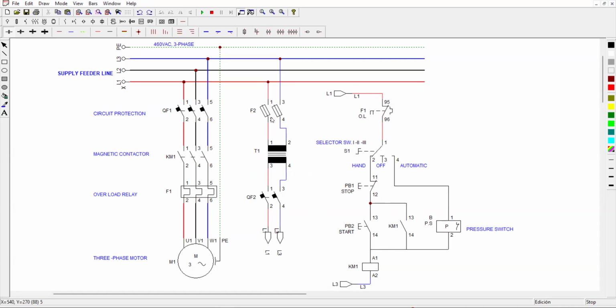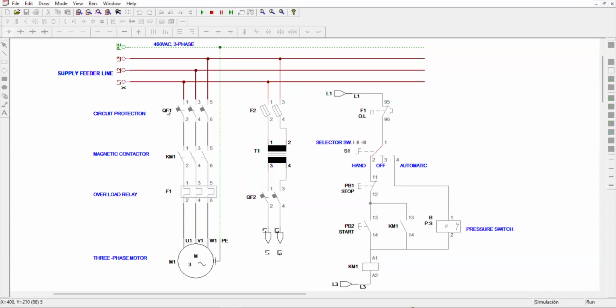So all in all, this will be our circuit diagram for the automatic and manual operation of a three-phase motor application. So in order to verify our circuit, we need to activate and simulate our circuit. So activate our circuit breaker for our motor power circuit, and we will also activate this disconnecting fuse for our transformer. Of course, we will activate this one, our circuit breaker for our control circuit.